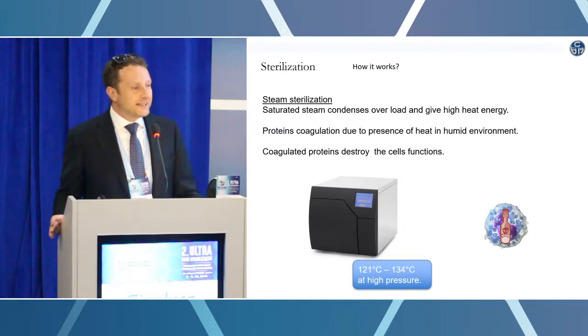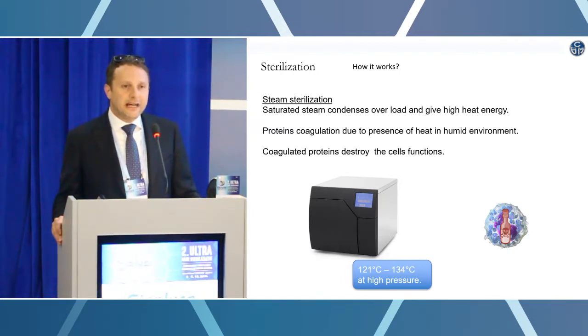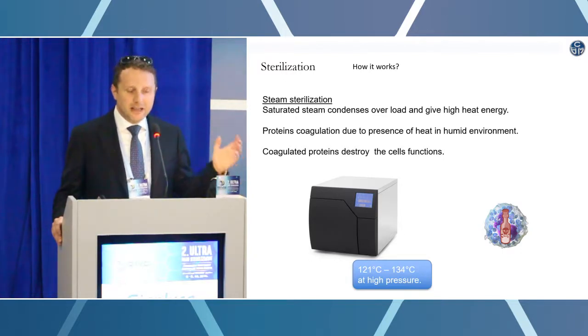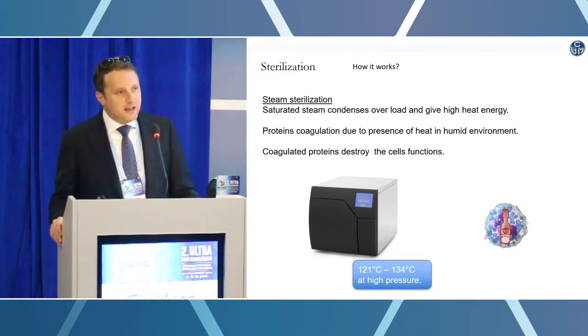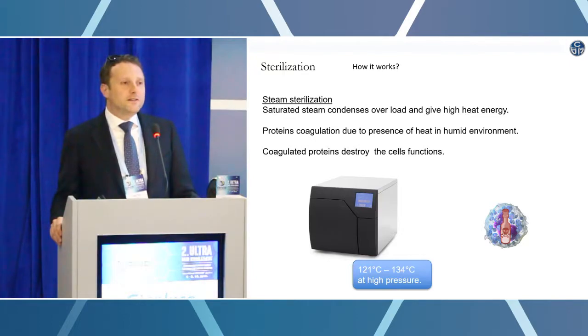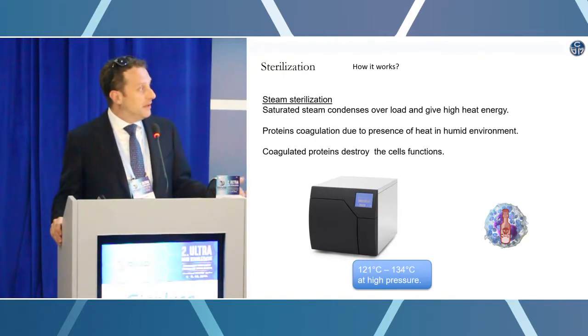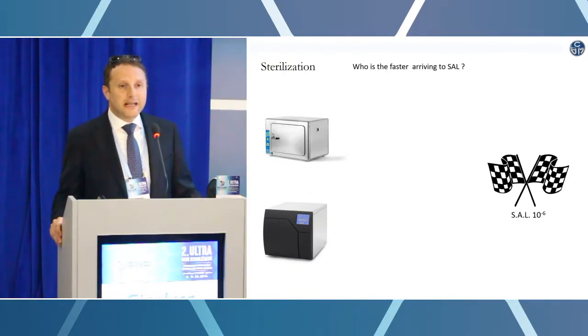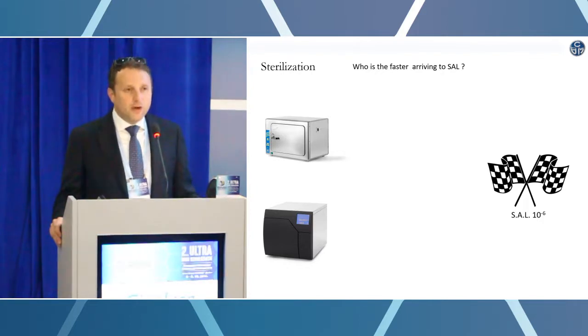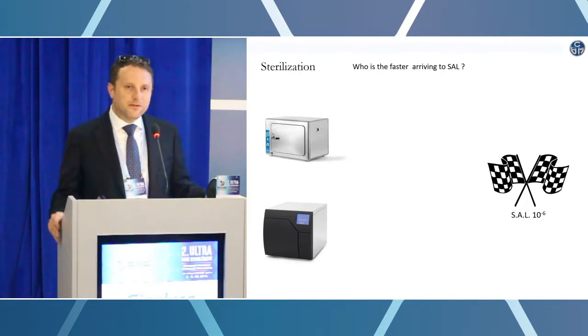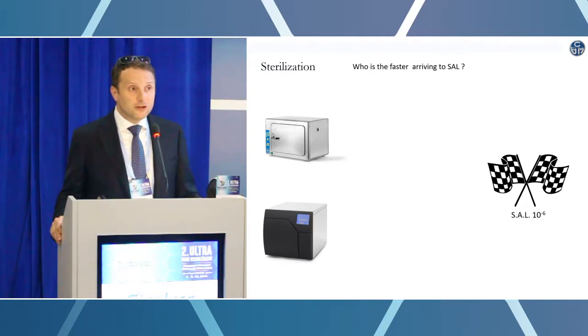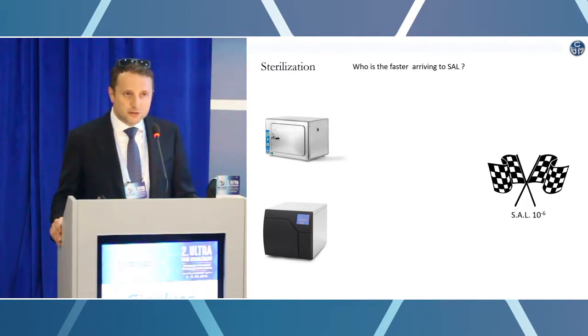So who is the fastest between dry sterilizers and small steam sterilizers to reach this sterility assurance level? By effect of the combination of steam, the small steam sterilizer will always be much faster than the dry heat sterilizer. On average, we have half of the time for the entire cycle to reach the sterility assurance level.